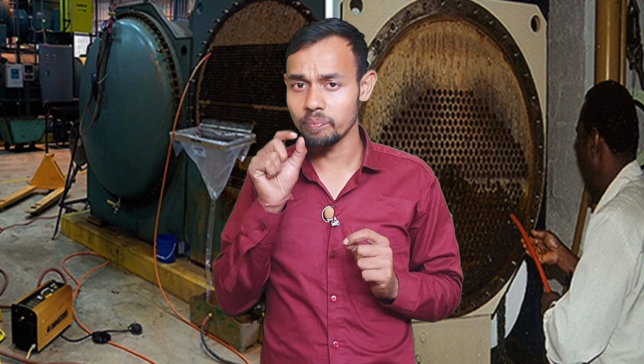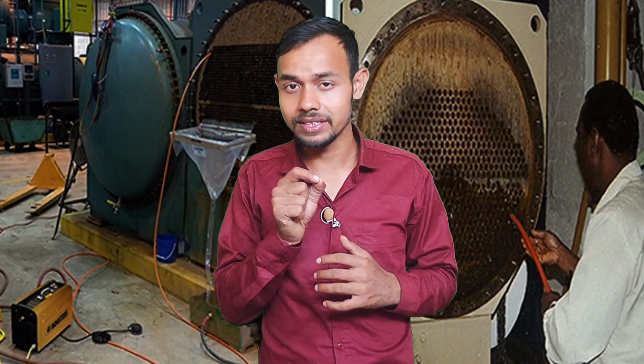Okay, and fourth is tube failure and leakage. Yes, scale plus corrosion leads to pinholes and tube leakage, refrigerant and water contamination. Refrigerant and water contamination lead to major breakdowns. Okay, fifth is cooling complaints everywhere. Yes, your rooms and offices are warm, the lobby is humid, guests are angry, technicians are stressed because of so many complaints, and the chiller cannot cool the water. Okay, descaling fixes everything.